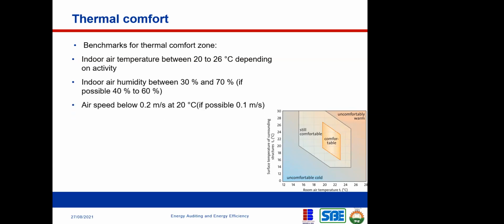So another factor is airspeed. Airspeed below 0.2 meter per second at 20 degrees centigrade, if possible, 0.1. This is not necessarily significant, but again, it's something that is worth knowing. And there is another factor that is often neglected, but also important: the carbon dioxide level. Now, this is applicable when you're in a conference hall where you have a lot of people. We breathe in oxygen and we breathe out carbon dioxide. When you're running an air conditioning system in that kind of situation, remember that your windows are closed, your doors are closed. If you're not careful, the level of carbon dioxide in that space might begin to increase, and it becomes a problem.